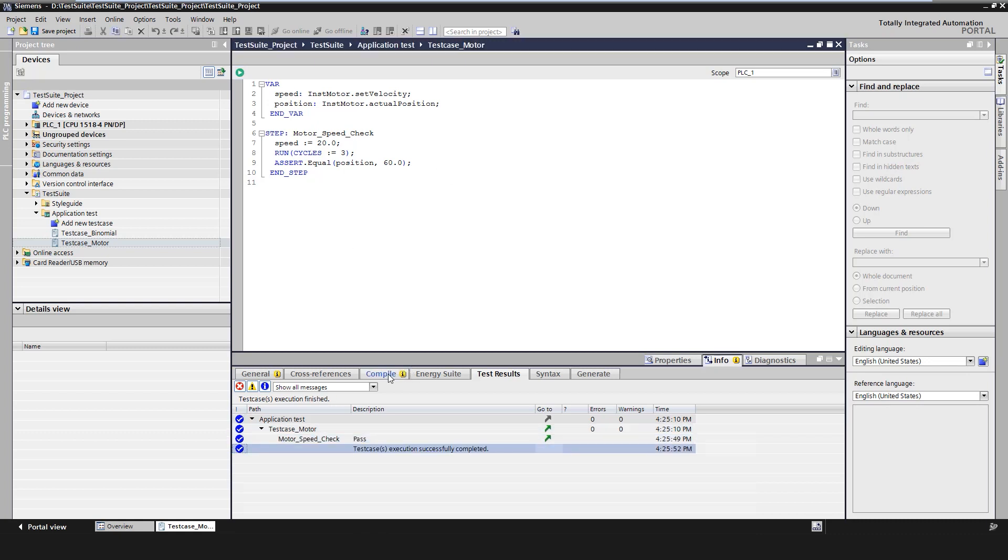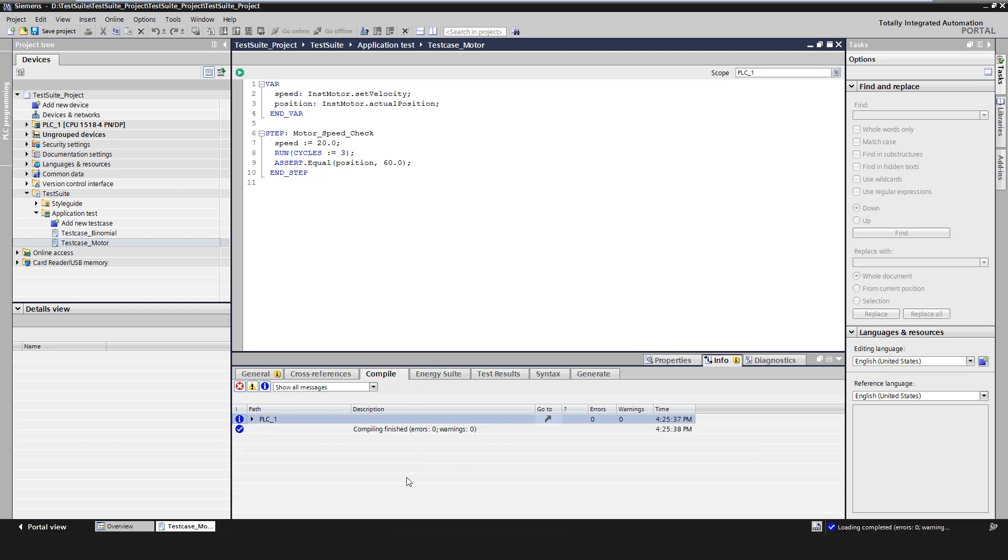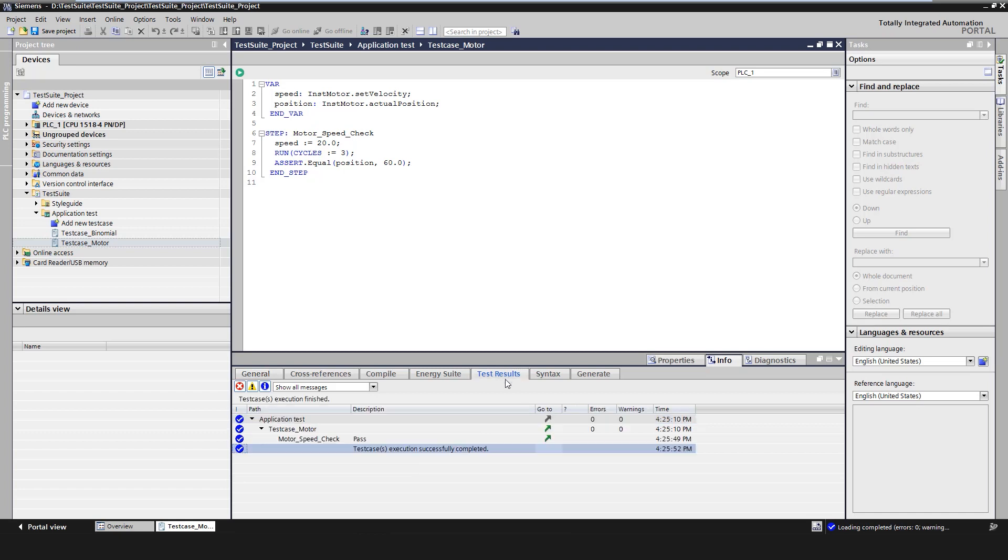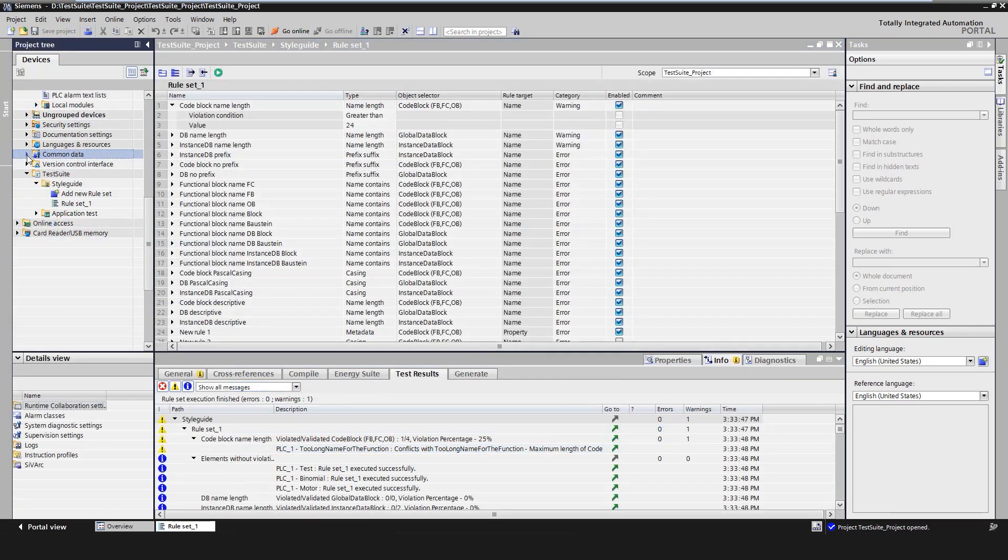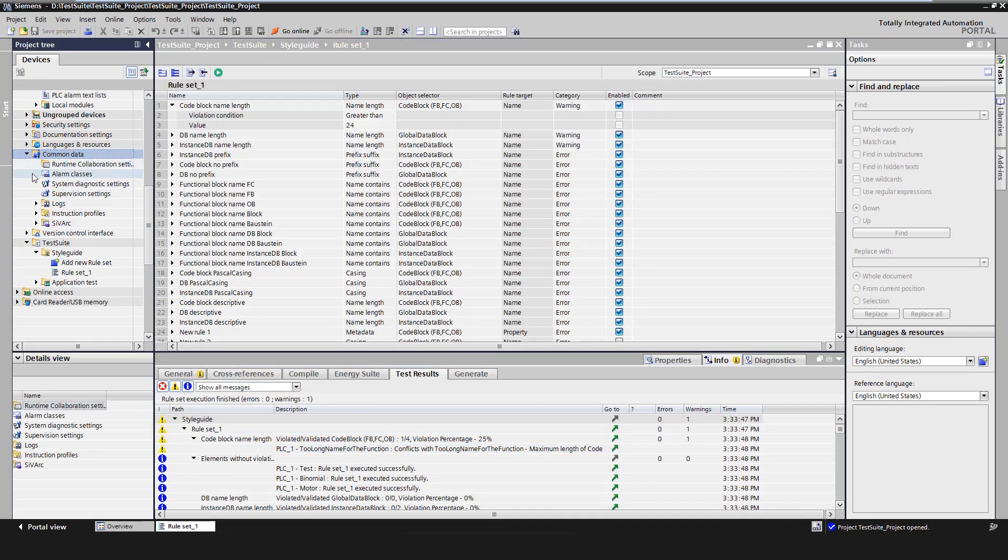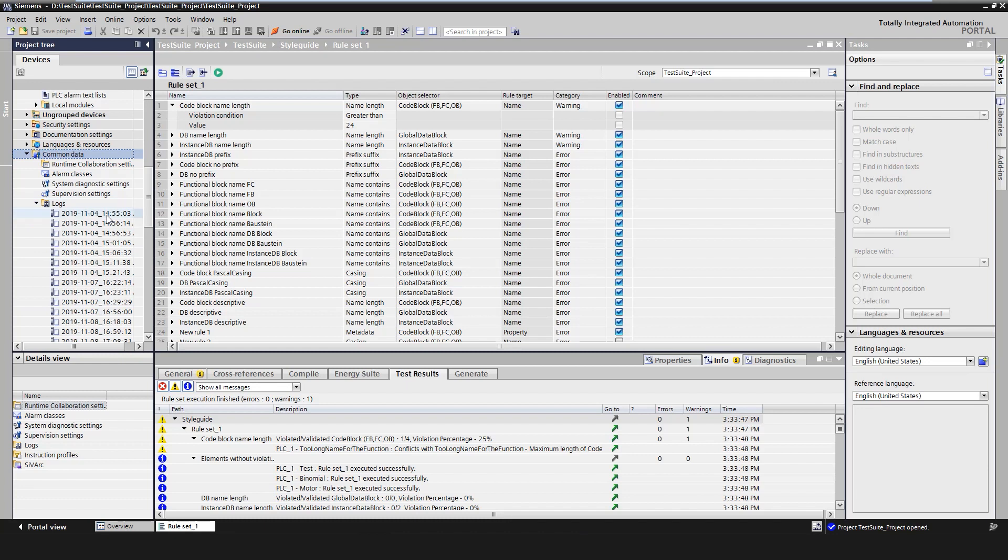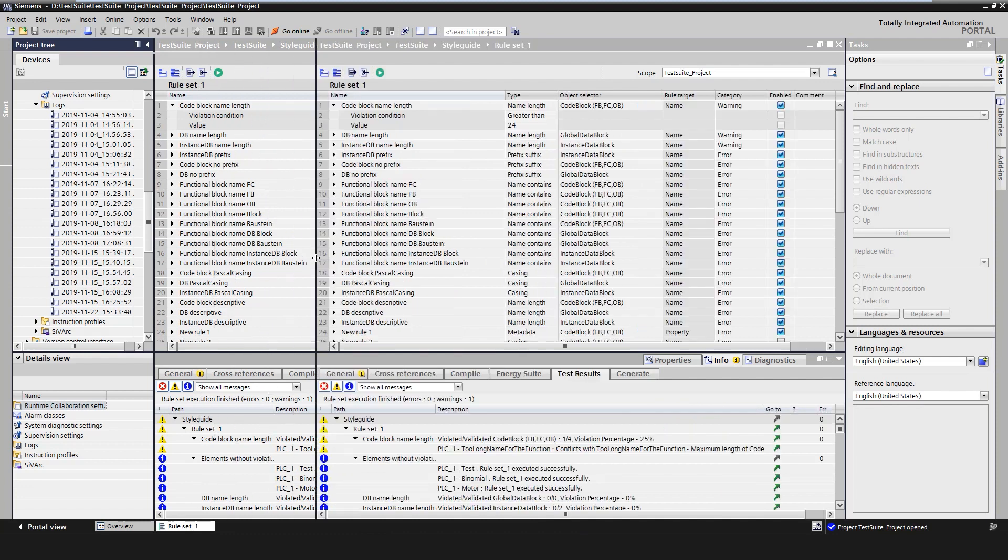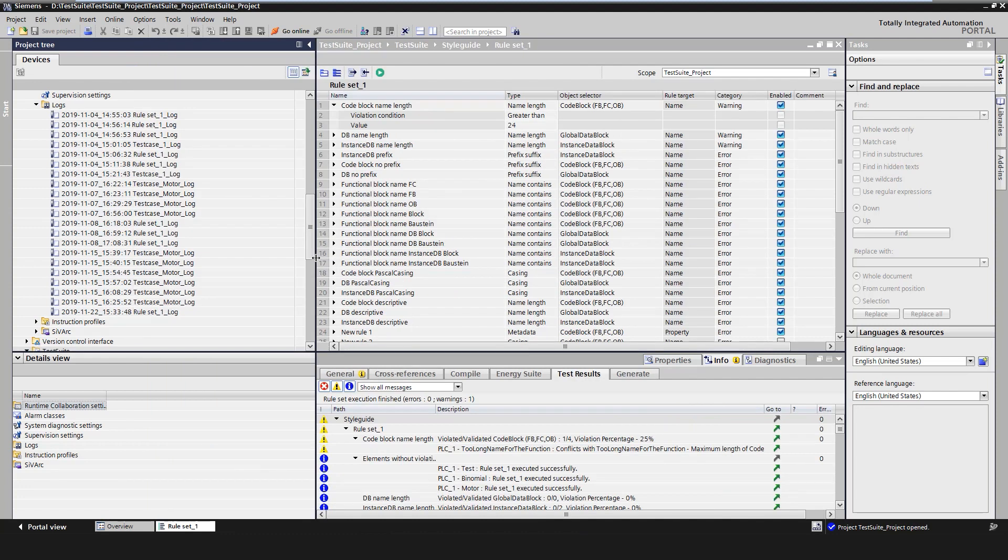First, compilation result in the tab compile. Here we can check whether the PLC program is compiled error-free in TIA Portal. Second, the download result in the tab general. Here we can check if a specific project is downloaded to a PLCSIM advanced instance. And third, the test result in the test results tab. All test results are stored in the TIA Portal project under Common Data in Logs. This documents the test execution in the project. This makes it possible, for example, to track when an error first occurred.